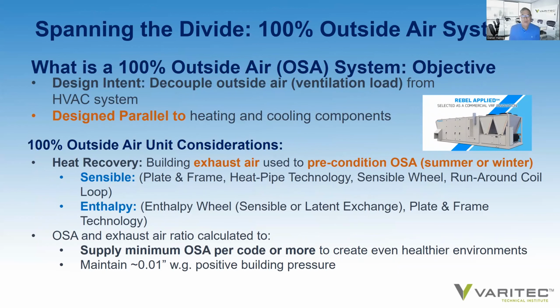The design intent of a 100% outside air system is to decouple the outside air or the ventilation load from the HVAC system. It is designed parallel to heating and cooling components. There are certain considerations on how a 100% outside air unit or DOAS unit is built. It incorporates heat recovery, where, if you want to optimize efficiency, you would want to use heat recovery, where building exhaust air is used to precondition the outside air.